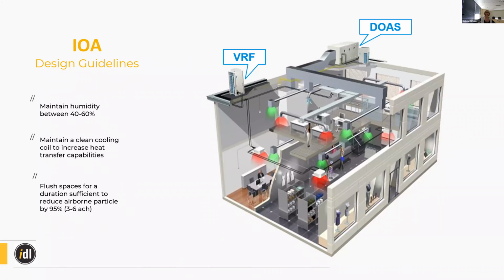And then speaking of humidity and temperature set points, ASHRAE recommends maintaining a humidity between 40 and 60%. And that is mostly for particle deposition. Again, sort of like the ionization, globbing on and making it easier to filter out. And then a big one is maintaining a clean cooling coil. So that's usually going to be your weakest link in taking in more outdoor air, is that the heat transfer capability of that cooling coil goes down as it gets dirty. So it's important to keep that clean so that you can continue to condition and dehumidify and humidify the air.